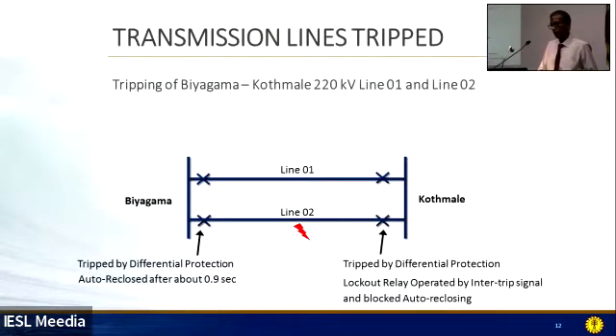After tripping of line 2, line 1 got the full load current between Kotmale and Biyagama, and it moved about 1,400 or 1,500 amperes. With this higher load current in line 1, we observed a permanent zero sequence current in the network, and that permanent zero sequence current became higher than the threshold of the backup earth fault protection setting. The setting is about 80 amperes, and initially, because of the auto-reclosing process of the single phase in the parallel line, a high single phase current was observed in line 1. Because of that, the relay got picked up.